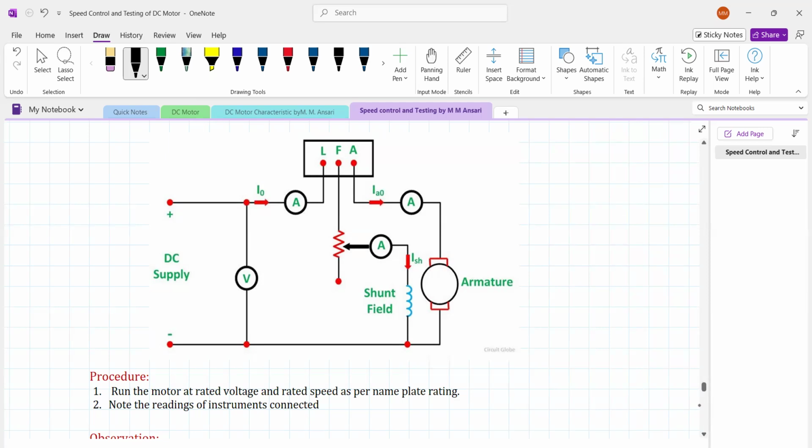This means that whether the DC motor is at load or no load condition, the current in the shunt field winding remains unchanged, whereas the armature current is a function of load. As the load increases on the motor, the armature draws more current. Therefore, the copper losses in the armature circuit and the brush copper losses depend upon the load condition. So these are the load losses.